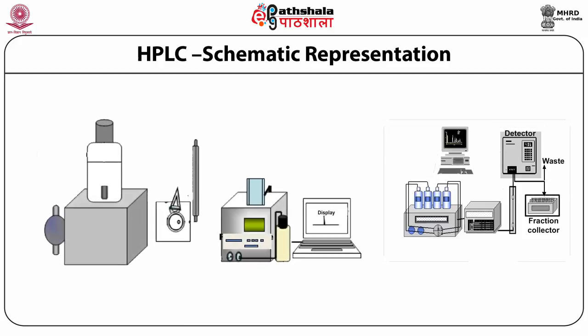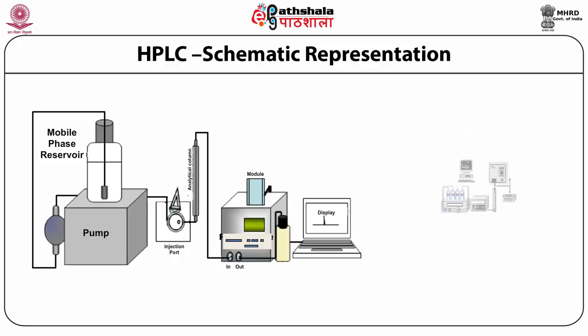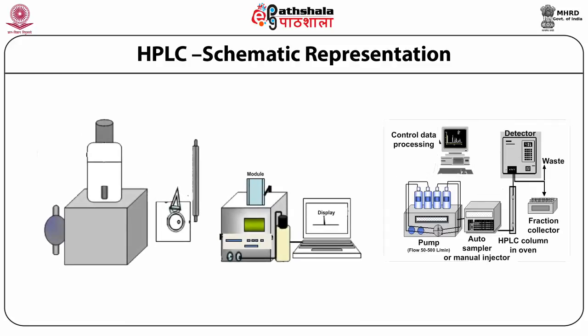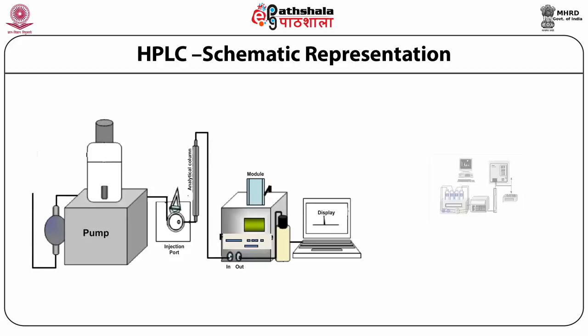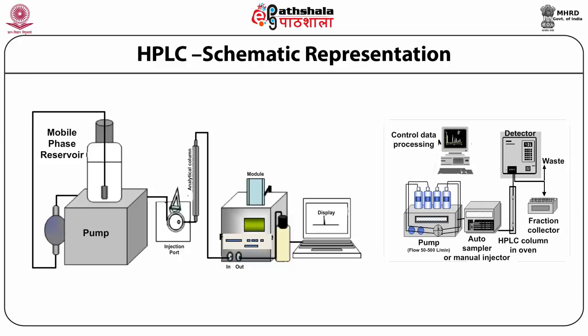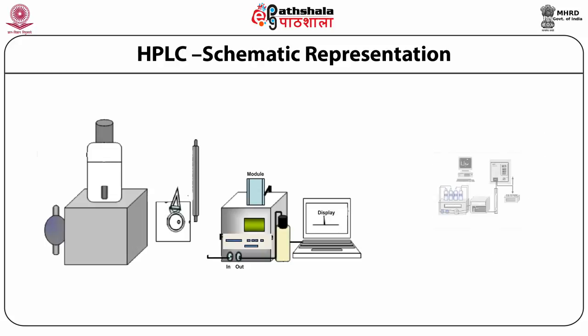Slowly the separation happens: a compound having higher affinity towards the stationary phase stays more time in the column, while one with low affinity elutes sooner. In a typical C18 column with a 1:1 acetonitrile-water or methanol-water mobile phase, acetone elutes first and then benzene. When compounds come out, they are identified using a detector. The signals generated in the detector are converted to electrical signals, integrated by software, and displayed as peaks in the output device.